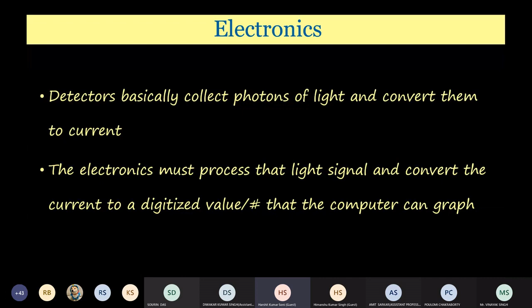The next part is called the analog to digital converter, or ADC. It takes the voltage pulse and converts it into a discrete binary number, depending upon the resolution, and those binary signals which are generated are converted into bin numbers. So analog to digital, just to understand: whatever current is coming in as an analog signal will be converted into digital, and those numbers will be used for the list mode values. They will give you how much intensity is coming from each cell, each event, and then they will be used for plotting the graph.